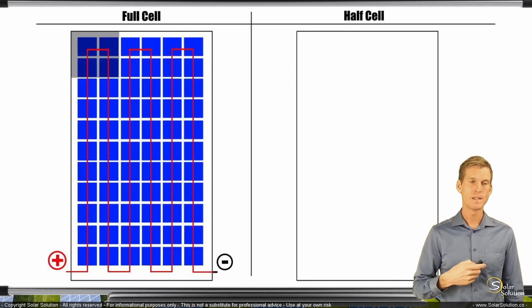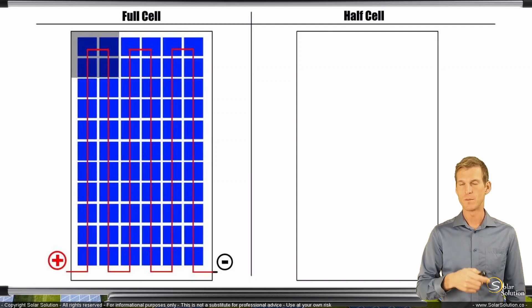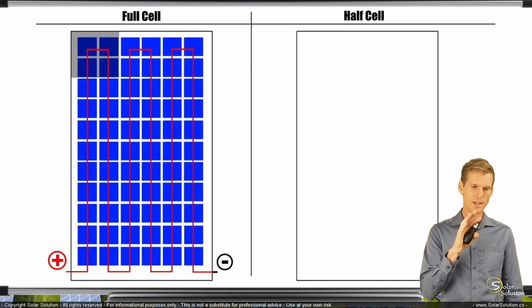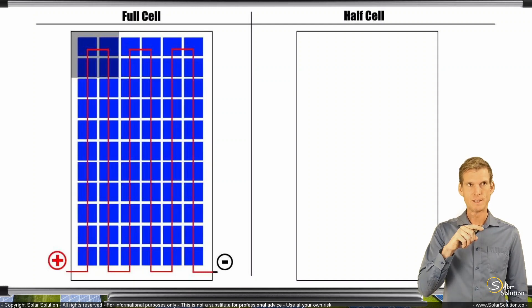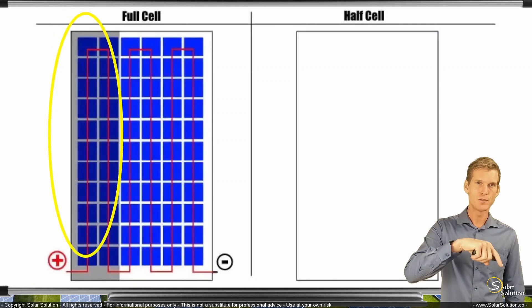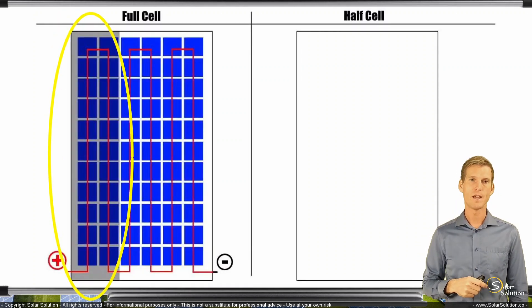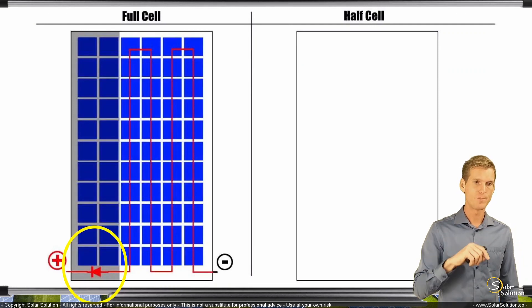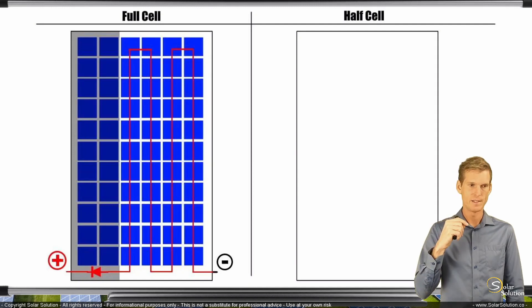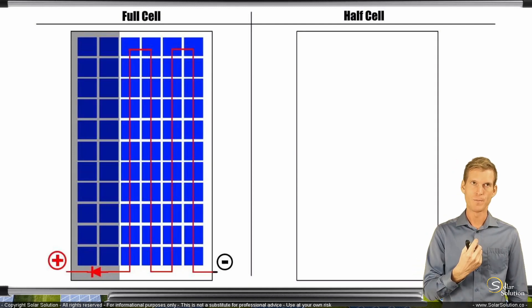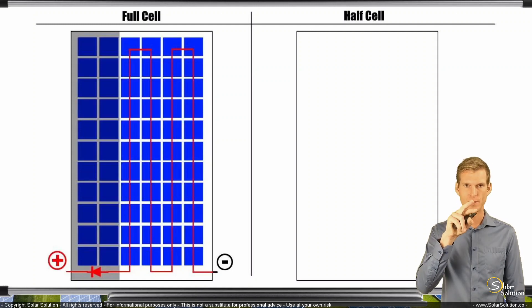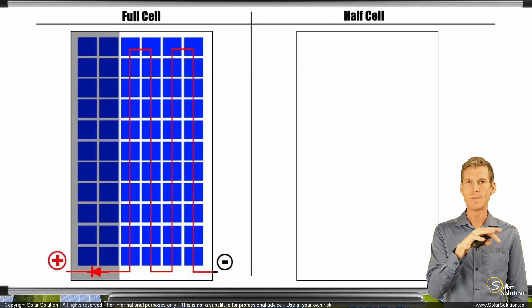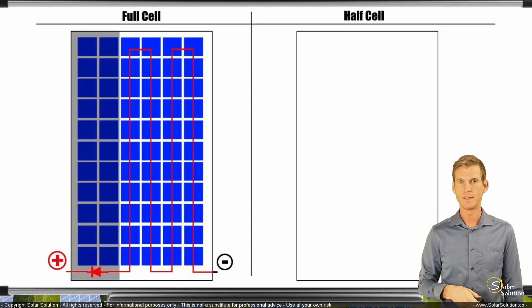So what they've done to kind of mitigate the negative impact from very local shading of a module is that manufacturers have installed bypass diodes. Typically what they do for these kind of modules is that they install one bypass diode for every two columns of solar cells. So they take the first two columns of the solar cells, they install a bypass diode, and then if those first four cells are blocked by a leaf, it's taking the first two rows completely out of operation. So it's accepting that it's losing one-third of the power output of the panel, but the other two-thirds of the panel will be operating at its full performance under the given conditions.